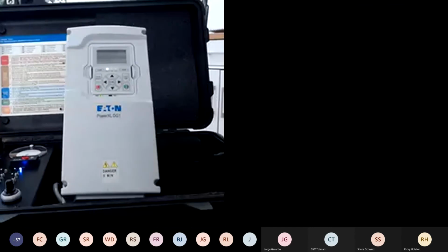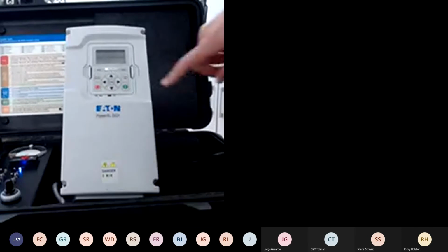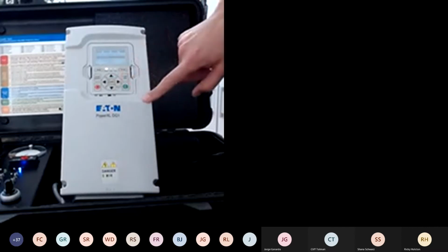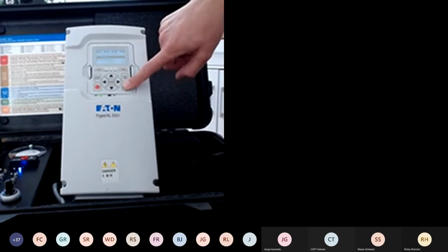So let me see here. I think we just got a message, but hopefully you can see the picture here. Let's start the machine on local. This is going to be straightforward. We're going to go through the local control, which means we can control the drive directly from the VFD. It is a very simple procedure. Once we properly program from your VFD motor nameplate, again, it's important that you use the correct values, your VFD will control the speed of your machine.